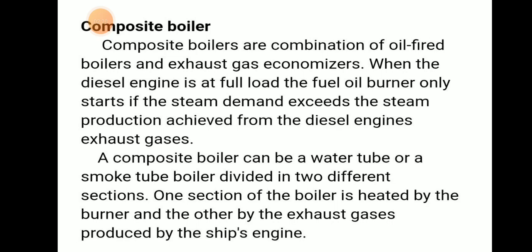Composite boiler — from the name, it is a combination of an oil-fired boiler and an exhaust gas economizer. When the diesel engine is at full load, the fuel oil-fired burner only starts when the steam demand exceeds the steam production achieved from the diesel engine exhaust gas.